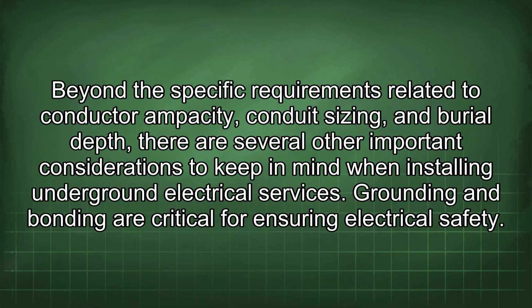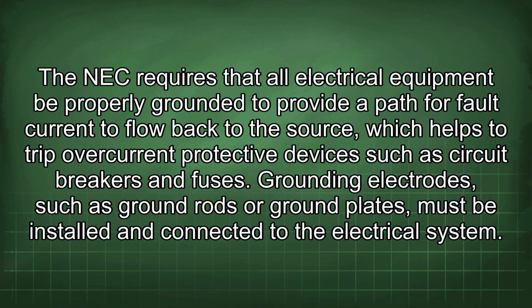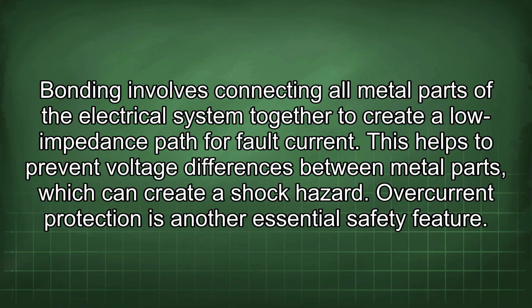Beyond the specific requirements related to conductor ampacity, conduit sizing, and burial depth, there are several other important considerations to keep in mind when installing underground electrical services. Grounding and bonding are critical for ensuring electrical safety. The NEC requires that all electrical equipment be properly grounded to provide a path for fault current to flow back to the source, which helps to trip overcurrent protective devices such as circuit breakers and fuses. Grounding electrodes, such as ground rods or ground plates, must be installed and connected to the electrical system. Bonding involves connecting all metal parts of the electrical system together to create a low impedance path for fault current. This helps to prevent voltage differences between metal parts, which can create a shock hazard.